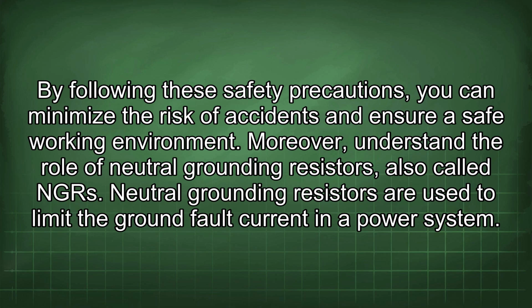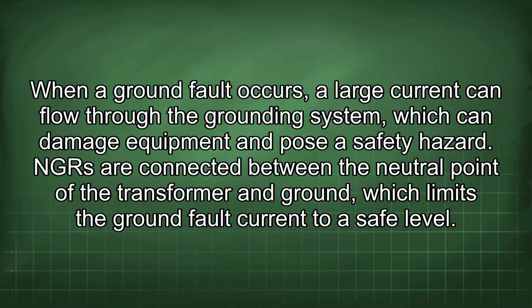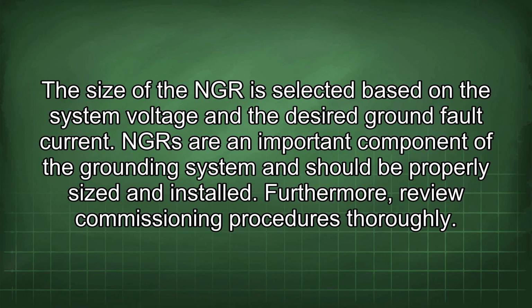Moreover, understand the role of neutral grounding resistors, also called NGR. Neutral grounding resistors are used to limit the ground fault current in a power system. When a ground fault occurs, a large current can flow through the grounding system, which can damage equipment and pose a safety hazard. NGR are connected between the neutral point of the transformer and ground, which limits the ground fault current to a safe level. The size of the NGR is selected based on the system voltage and the desired ground fault current. NGR are an important component of the grounding system and should be properly sized and installed.